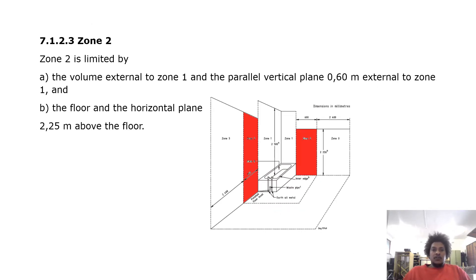Zone 2 is limited by the volume external to zone 1 and the parallel vertical plane 0.6 meter external to zone 1, and the floor and horizontal plane 2.25 meters above the floor. So it is basically next to zone 1, from the floor up to 2.25 meters. Zone 1 stretches a bit further as it is 2.5 meters above the ground, whereas zone 2 has a height of 2.25 meters above the floor.